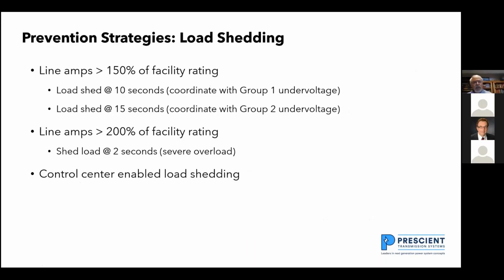The prevention strategies have to include load shedding. Right now, all my protective systems are set up to allow overloads to occur indefinitely. And we would like to put in load shedding. So if I get 150% of a facility rating, I start doing load shedding at 10 seconds if I'm using the group 1 under voltage settings. And I would start doing load shedding at 15 seconds if I'm using the group 2 under voltage.